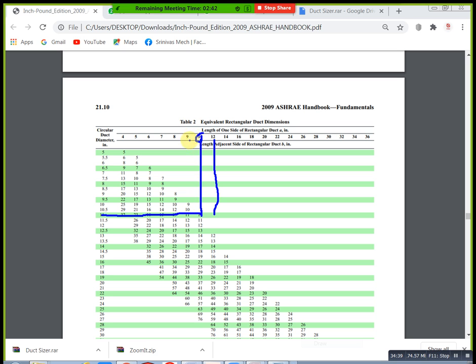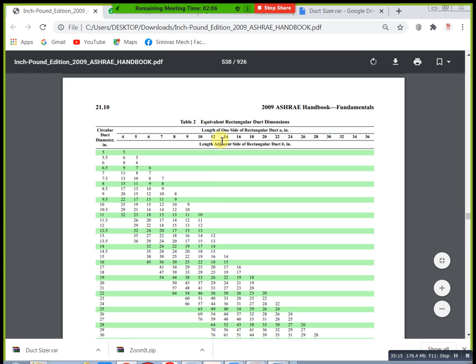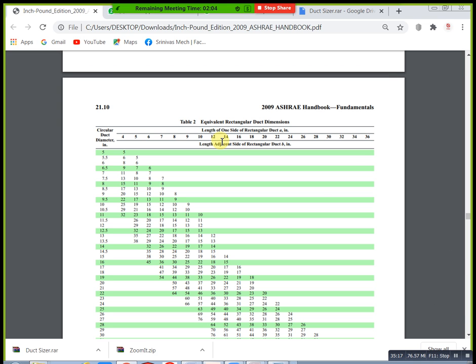Why, I will show. For example, we have our starting duct height, how much? 14 inch, right? From the machine we started, our duct size is 14 inch. Always take below the 14 inch height. You don't mention above the 14 inch height. Why? Because we are taking our height based on site clearance. For example, if you increase your height, it will automatically contact the other services or your slab or your ceiling like that.